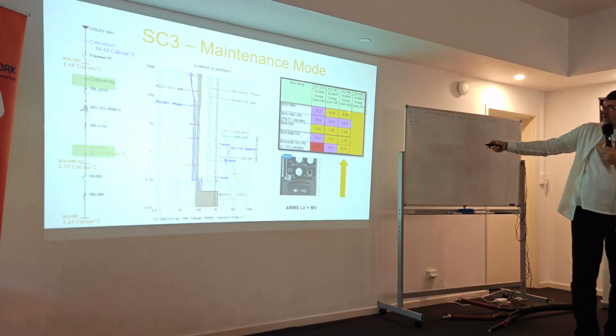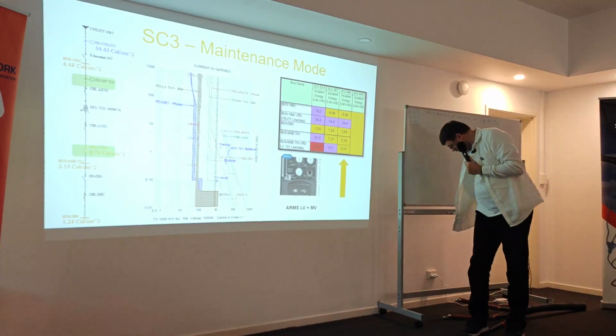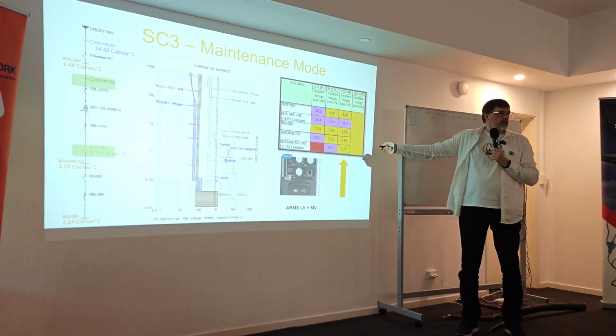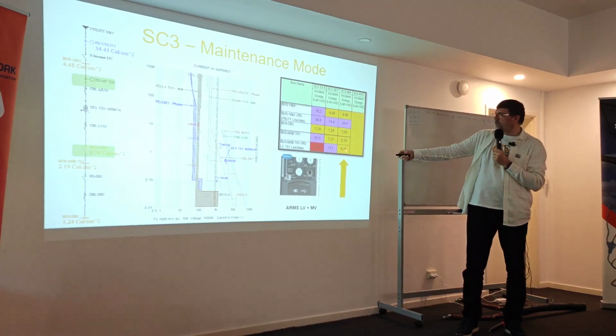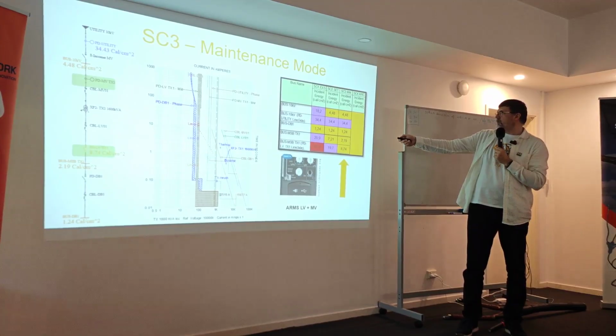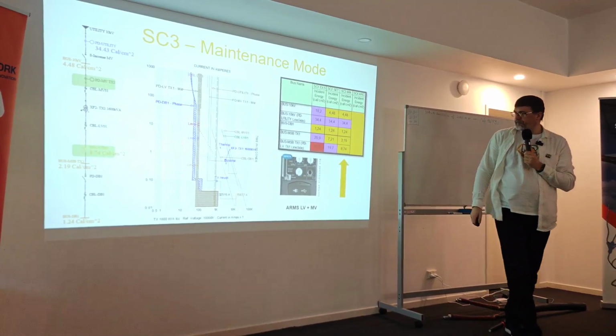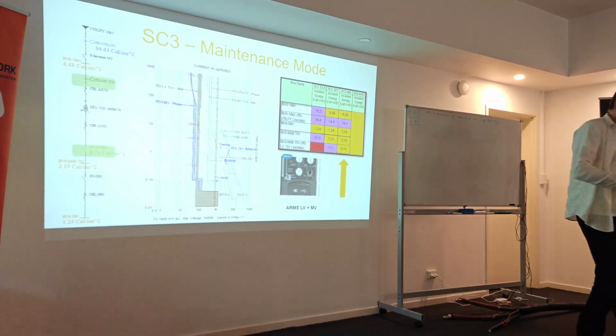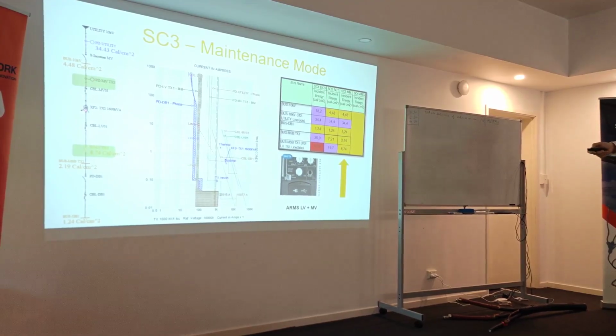So we drop it, and then you can see that the results are changing. From the reference point, we go from 20 to 2, or from 7 to 2, depending on how you want to look at it, and from 90 to 8. And on the medium voltage one, this one is 4.4, no huge difference, because this one stays the same. It's used here for protecting the transformer and the low voltage, yeah? It's done here purely because of this line side, and it doesn't work for the medium voltage bus, yeah? Otherwise I'd have to do it here and then drop it for the medium voltage. So you can see we are pretty much below. Normally I use below 12 calories as a reference, so it's somewhere around 8 already here, so it's good.